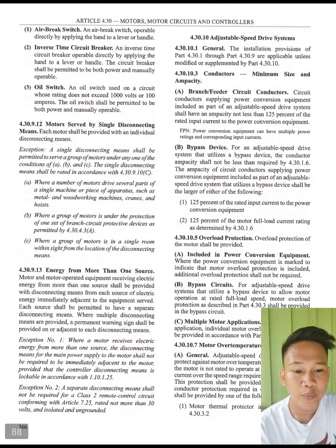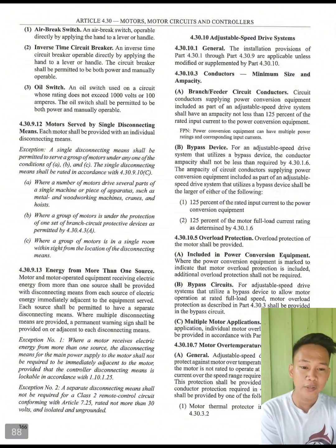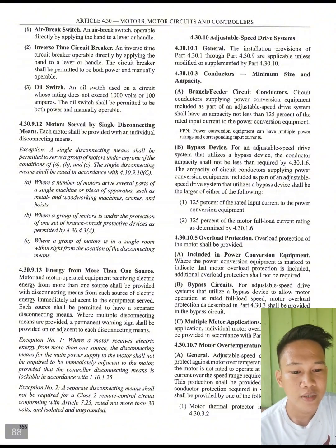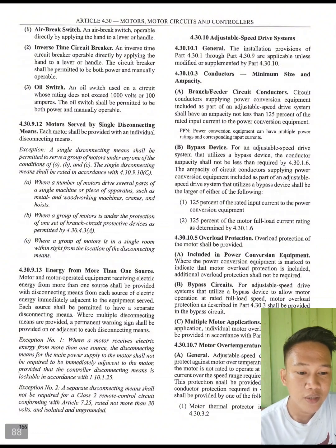Next, we have 4.30.10. Adjustable speed drive system. 4.30.10.1 General. The installation provisions of Part 4.30.1 through Part 4.30.9 are applicable unless modified or supplemented by Part 4.30.10. So, 4.30.10.3 Conductors, minimum size and ampacity. So, A. Branch feeder circuit conductors. Circuit conductors supplying power conversion equipment included as part of an adjustable speed drive system shall have an ampacity not less than 125% of rated input current to the power conversion equipment.